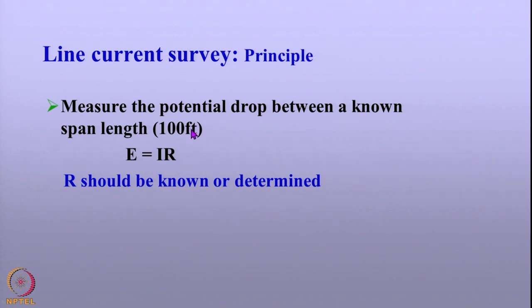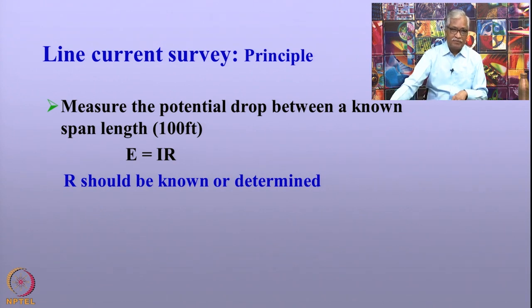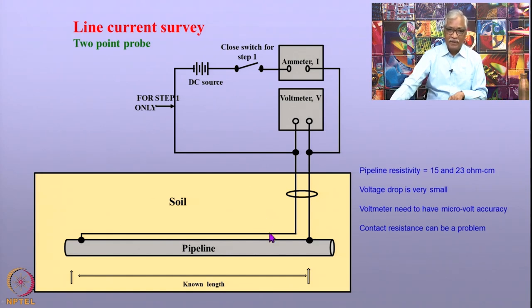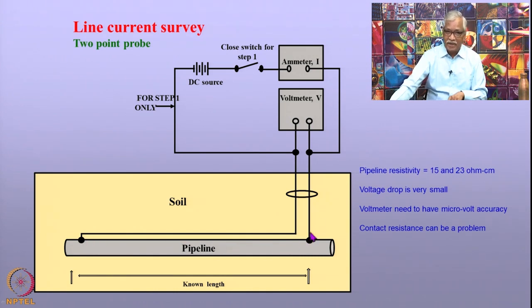Typically about 100 feet of pipeline is selected for measuring pipeline current. There are two types of line current survey techniques. The first is the two-point probe, which is relatively simple. It involves measuring the potential across a known segment of the pipeline length using a millivolt meter to measure the potential drop caused by current flow. If the resistivity is known, the current flowing in the pipeline can be determined.